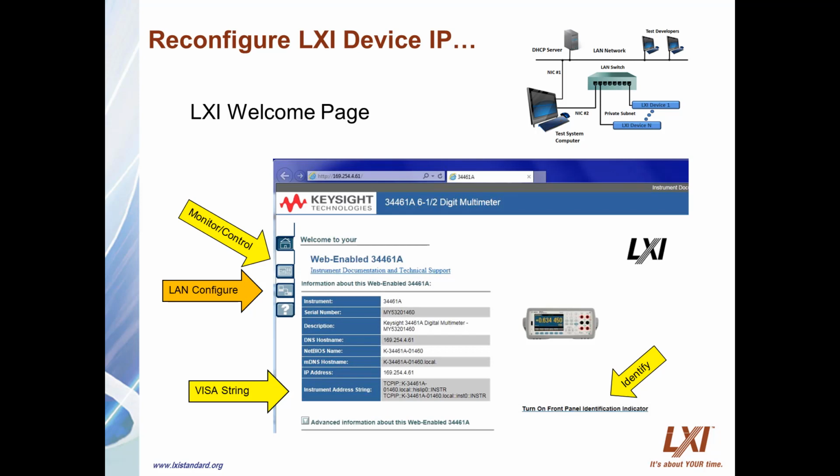Here's an example of the welcome page for a particular LXI device. Off to the side here we have an icon pointing towards web monitoring and control. You've got the VISA string down below, which you can use later for programming this particular device. And you've got something over here called Identify. Because if you have multiple LXI devices that are all the same model number, you can press this ID button and an indicator will flash on that device, either on the screen or as a blinking LED, so you can identify which device you're actually talking to.